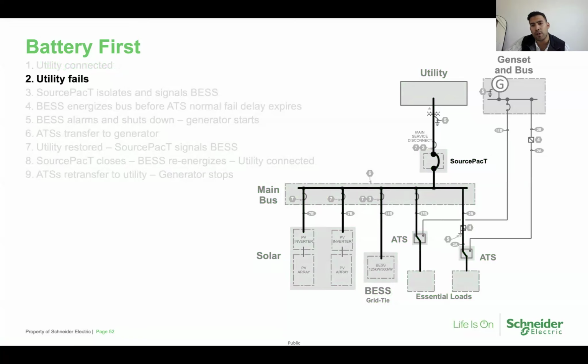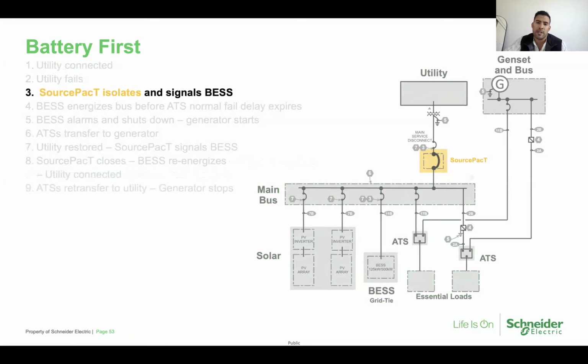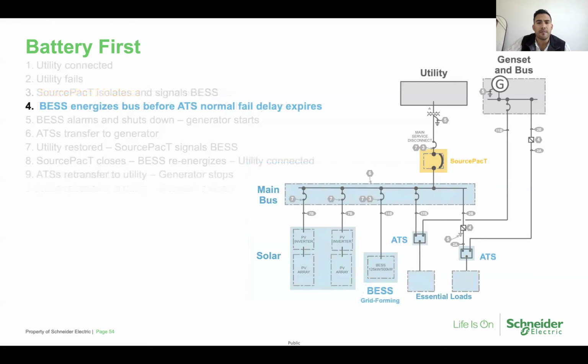Your main bus will go dark. SourcePacT will isolate and signal the battery. So again, we're going through the same animation here where we're calling on the battery to be the primary emergency power source. Ideally, again, these energy storage systems are sized for 3 to 4 hours of runtime, some even larger. But in the event that an outage should occur larger than that, or for a longer duration, you would want that generator to be basically the secondary emergency power source in your system.